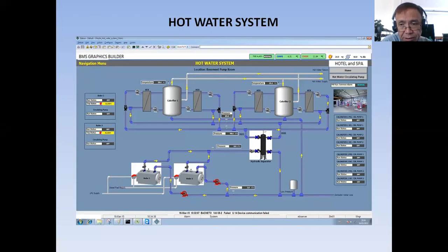What I did here is they have their own control panel. I specifically asked for the monitoring points as specified in their material submittance. So I asked the boiler status, the circulating pumps status, and the rest of the monitoring points, the temperatures.